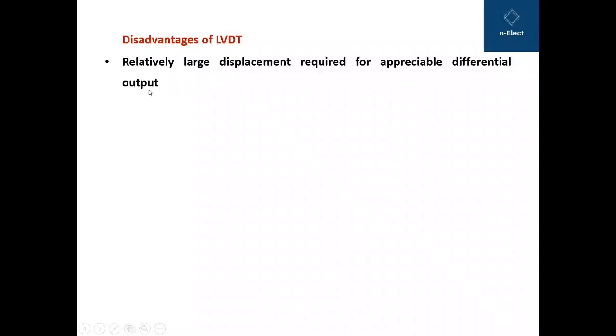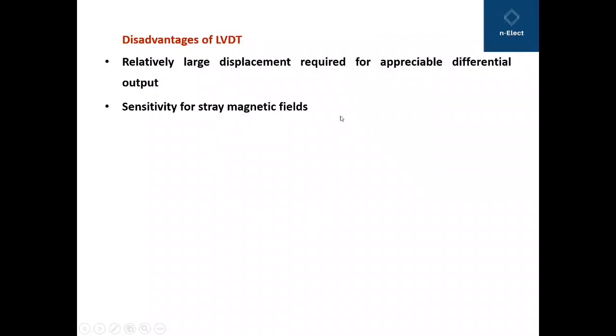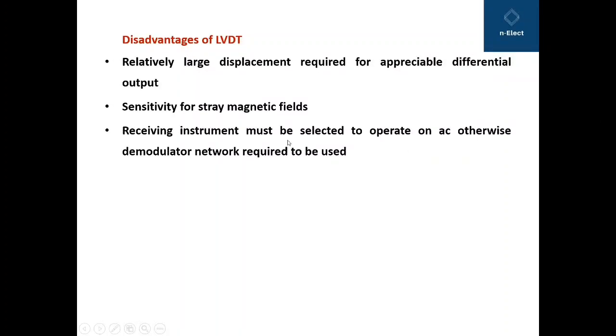LVDT is also associated with some disadvantages. First, a relatively large displacement is required for an appreciable differential output. Second, it is sensitive to stray magnetic fields — unwanted fields in the vicinity of the LVDT that may affect the differential output. Third, the receiving instrument must be selected to operate on AC; otherwise, a demodulator network is required, since LVDT output is AC.